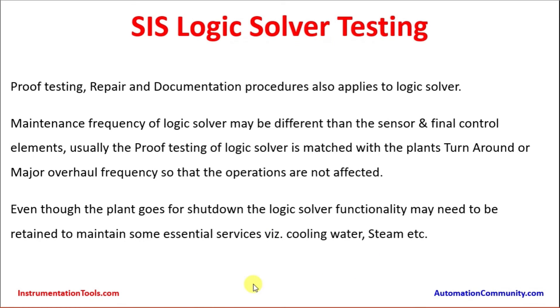Even though the plant is shut down, it does not mean the SIS logic solver can be stopped — it must keep running. The outage for the logic solver may be only one day or at most two days, depending on plant criticality. Within this window, all required proof testing must be completed, with the responsible project engineer conducting the testing with the help of maintenance personnel.